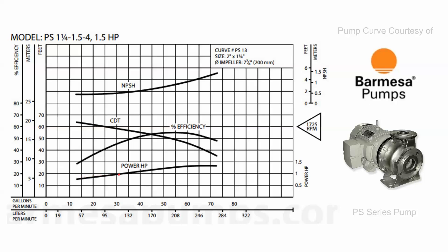When you look at the performance curve, operating at one horsepower is adequate up to about 30 gallons per minute. If you needed more than that — for example, operating at 60 gallons per minute, which is a very efficient spot — you would look at the power curve and determine that you need to purchase the one and a half horsepower configuration so that the motor will not overload in that application.